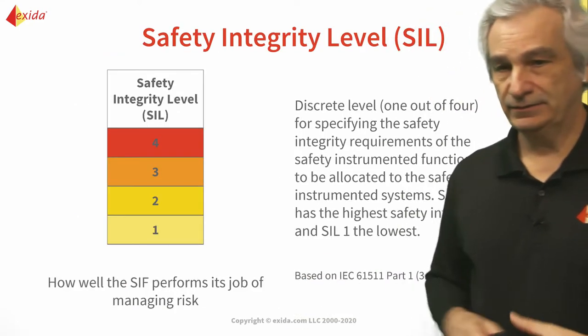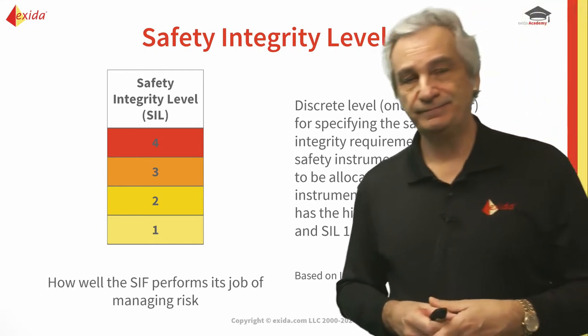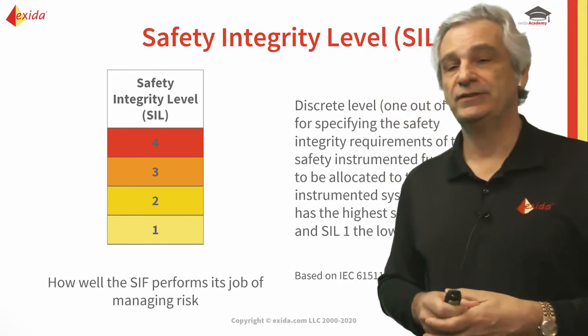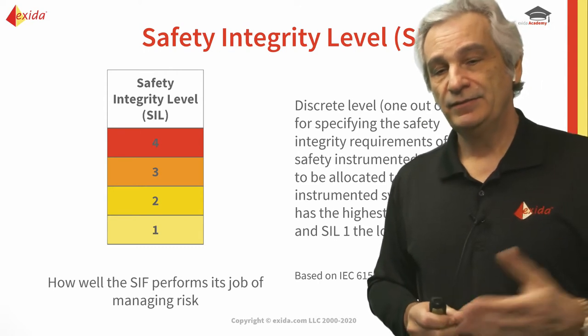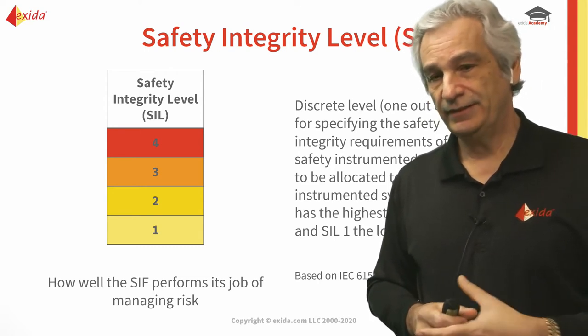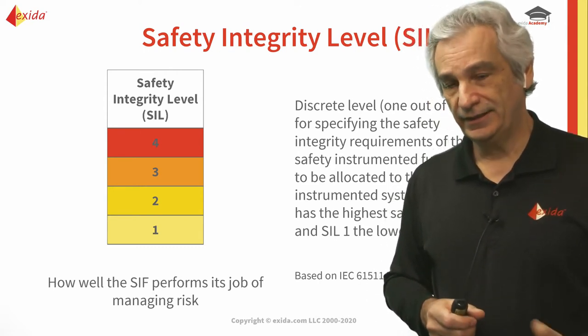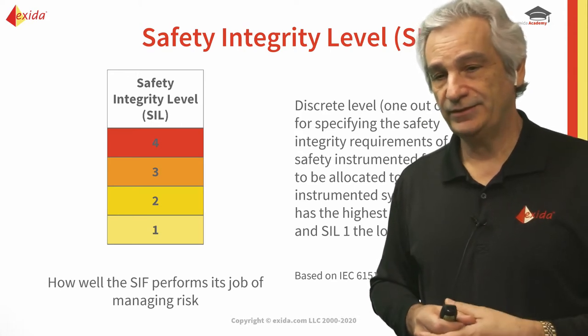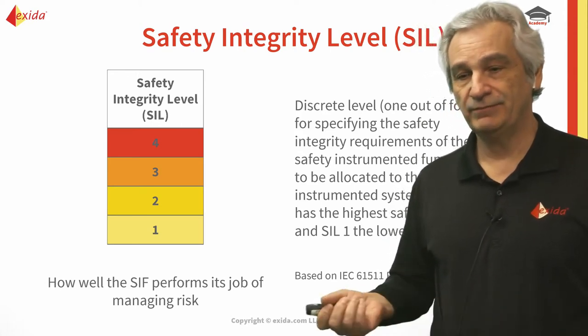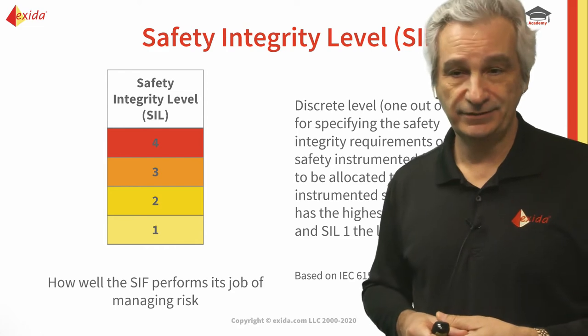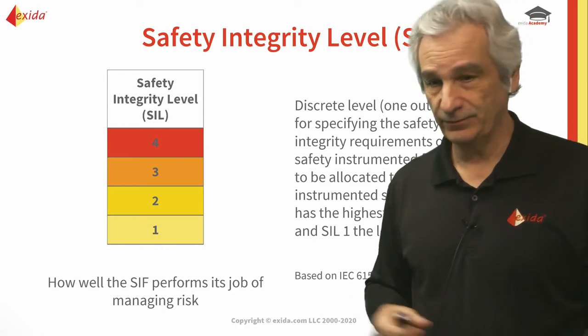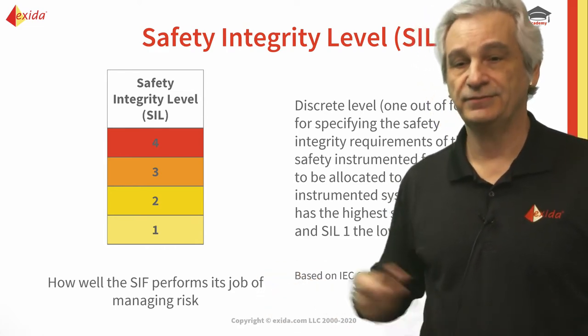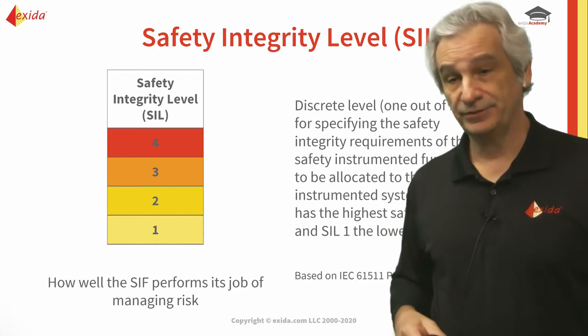So what are the safety integrity levels? There are four safety integrity levels defined: SIL 1 being the lowest, SIL 4 being the highest. They're typically an order of magnitude apart. SIL 1 would be anywhere between 1 to 100, SIL 2 is 101 to 1,000, SIL 3 is 1,001 to 10,000, and SIL 4 is above that.